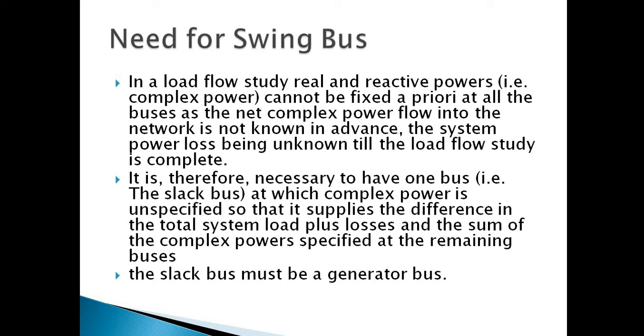Okay, so that is the same thing which I have told you. A slack bus should be the reference bus, which we cannot specify its power. Because when we solve the system, in order to solve the equations, one bus is kept there so that it supplies the difference of the power that is created in the solution.